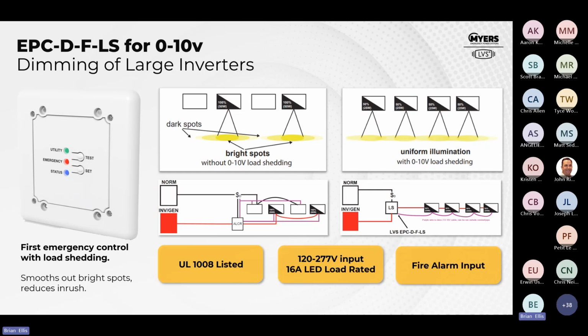If you have a centralized inverter, a large inverter, or you have a generator, and you still want to utilize load shedding, you can use this load shed device. Think about it from one perspective: on our corridor, we might have a lighting control device, we might have our ALCR, but we're still wiring every other fixture, right? So that's additional wiring for the contractor. And then we have these dark spots, right? So when emergency mode happens, we have this fixture on at full light output, this fixture on at full light output, and these fully dark.